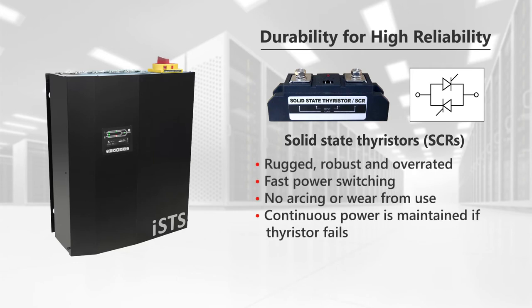The switching components are fully solid-state thyristors, which are rugged, robust, and overrated to withstand large fault currents. These perform fast power switching and do not arc or wear out from use. Continuous power is maintained in the rare event of a thyristor failure.